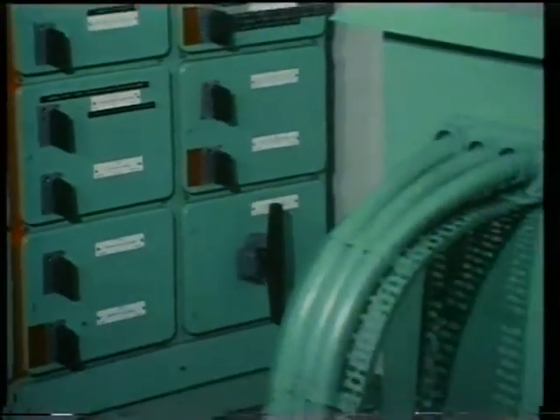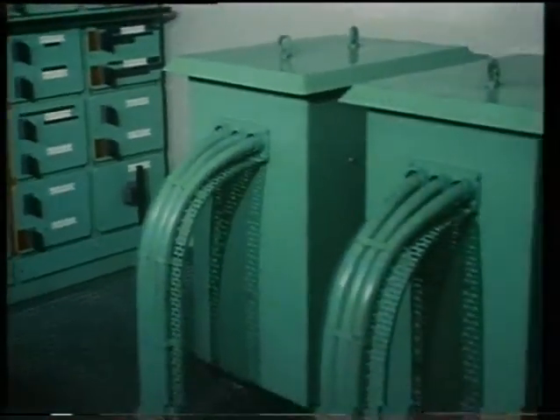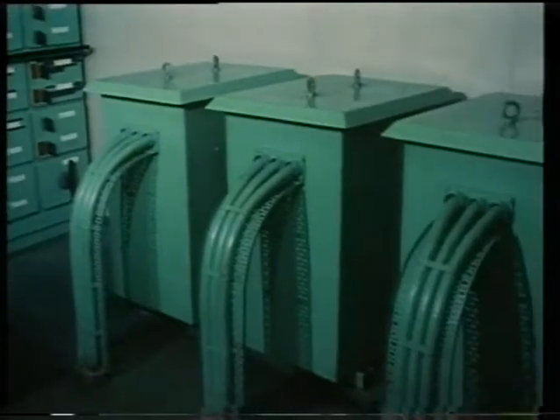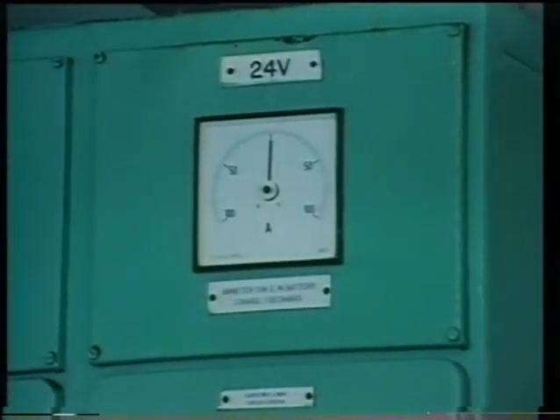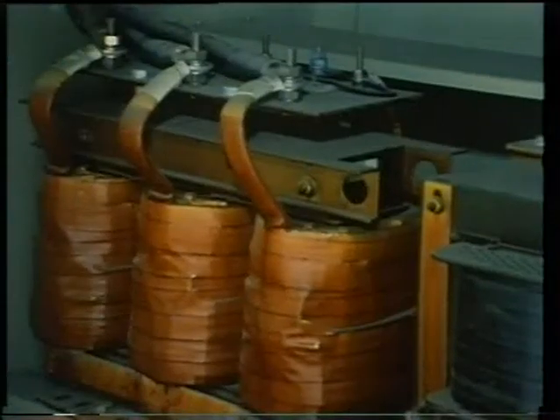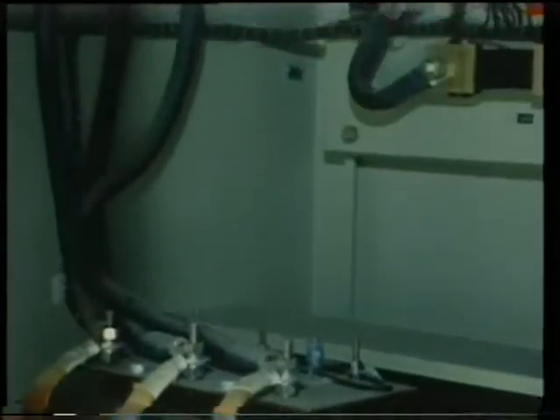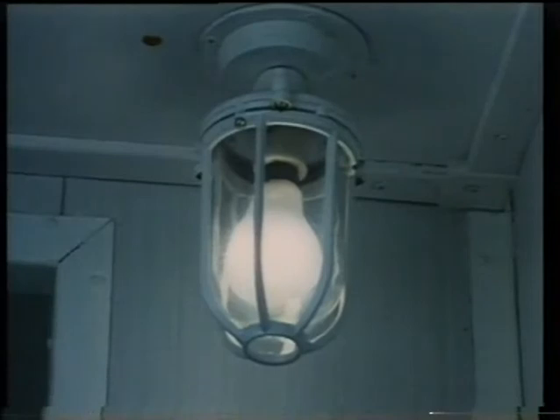One of the feeder circuits supplies a bank of transformers, which reduces the voltage level to 220 volts, or in some cases, 110 volts for lighting and other consumer units. Another circuit provides typically 24-volt DC supply through a transformer rectifier system.